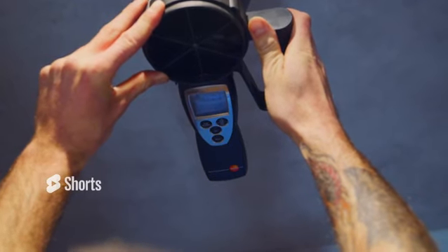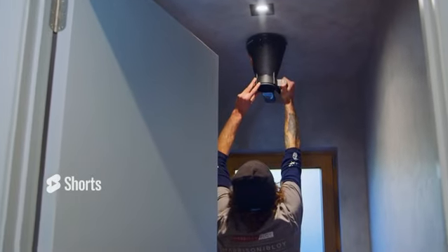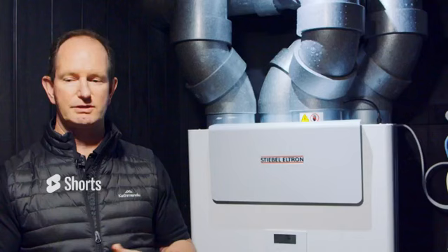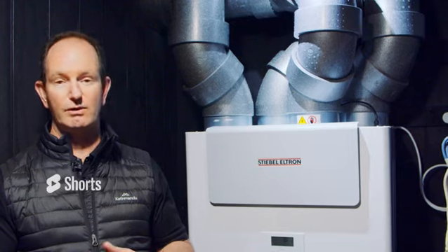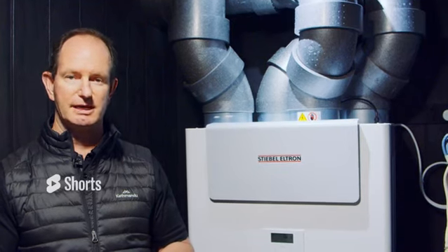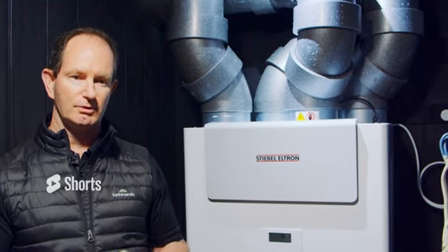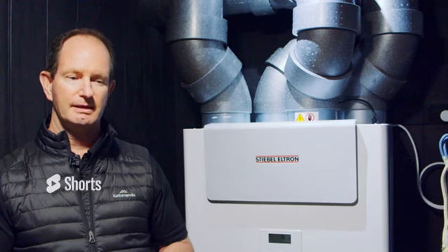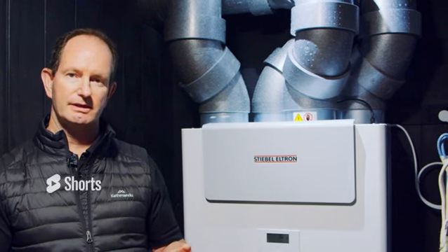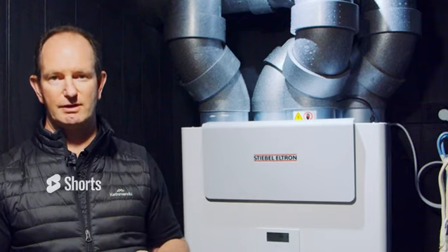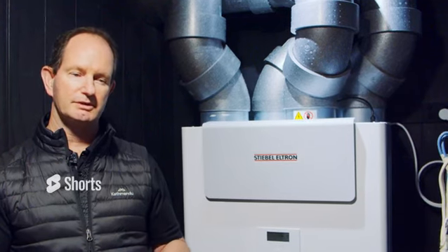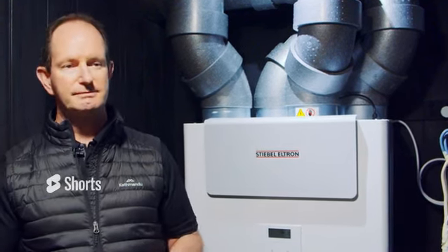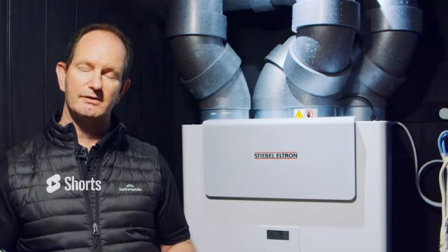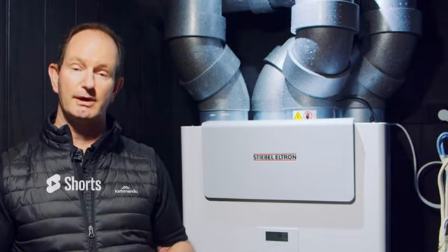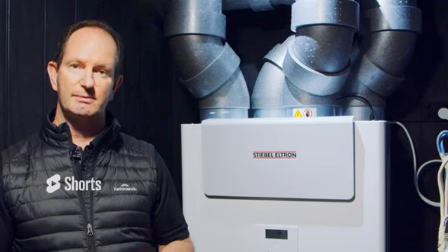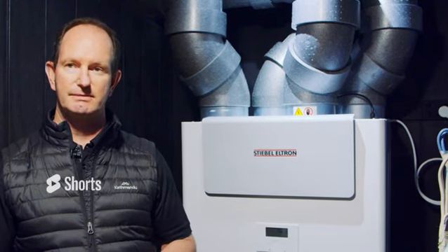If we look at all of the living spaces and the air volumes being injected into those spaces versus the wet rooms and all of the return air volumes added together, those two total bottom line values must be the same. And what that means is that we're not pressurizing the house and we're not depressurizing the house. But also what's happening with the heat exchanger core is that the same volume of air is passing through the heat exchanger core on both sides, and that gives us our maximum heat recovery efficiency.